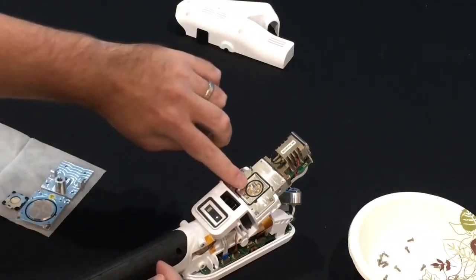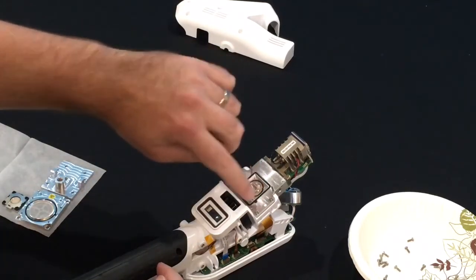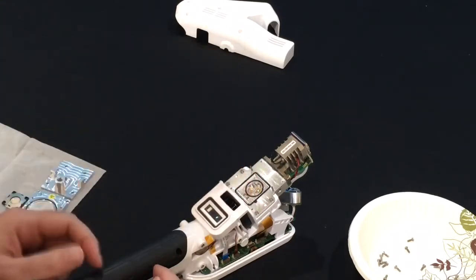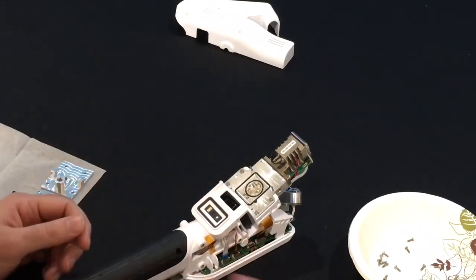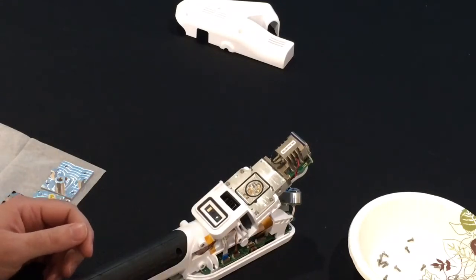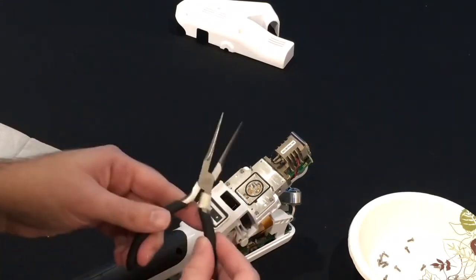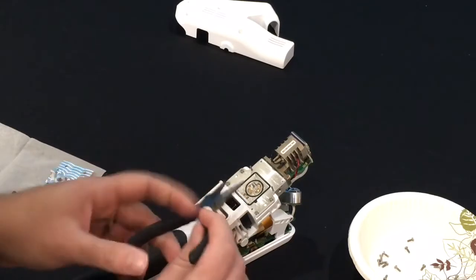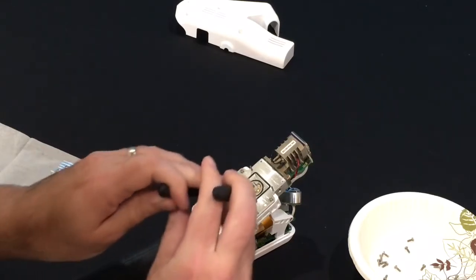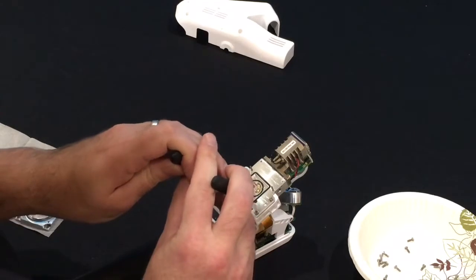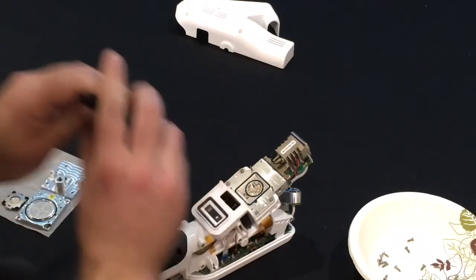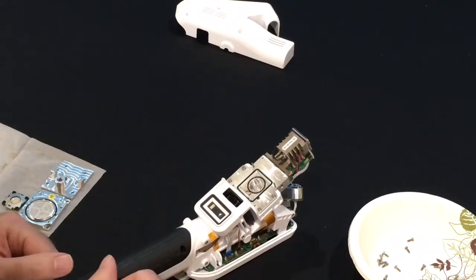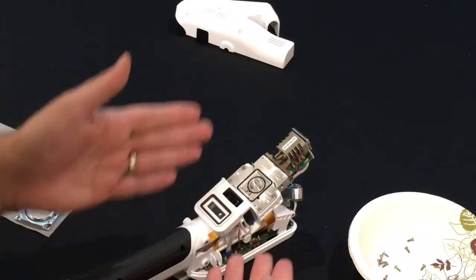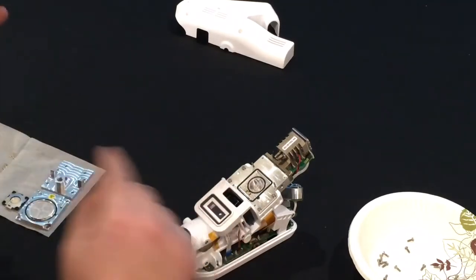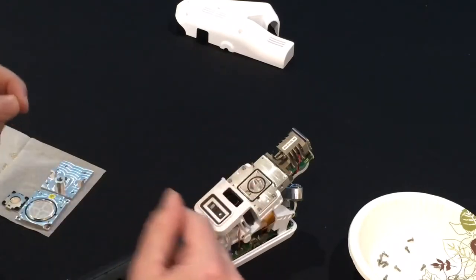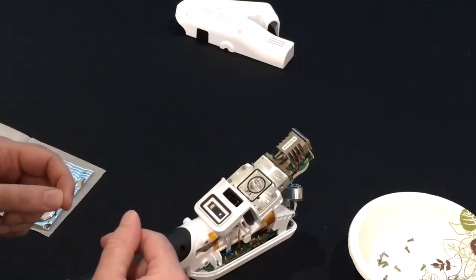Now, inside here, inside this ring, we have 8 buffer beads. We need to remove those so that they don't interfere with the calibration process. For this step, you should use gloves or tweezers, forceps, needle nose pliers to remove them. Make sure to set them aside on Kim wipes or a sterile environment.